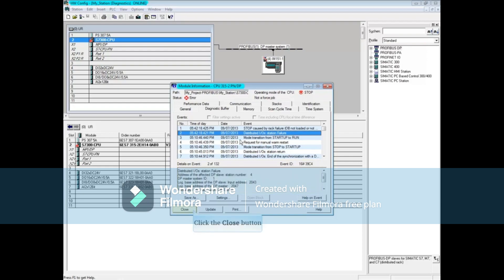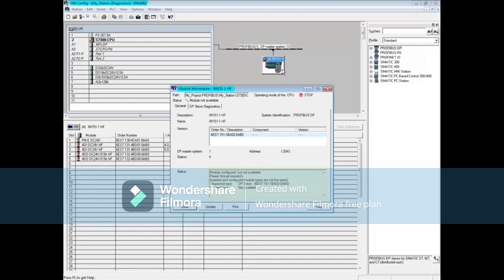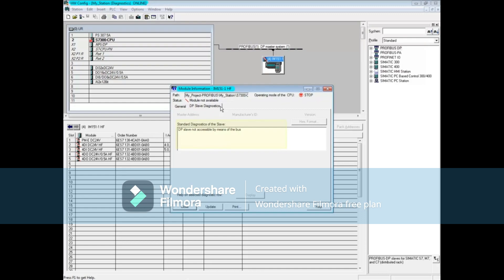Close the Module Information Tool. Let's take a look at Station Diagnostics. To open its Module Information Tool, double-click on the IM151-1 with Profibus address number 4. On the General tab, we see that the module is not available, which agrees with what we see graphically. Click the DP Slave Diagnostics tab. This shows us that the station is not accessible by means of the bus, that is, Profibus.